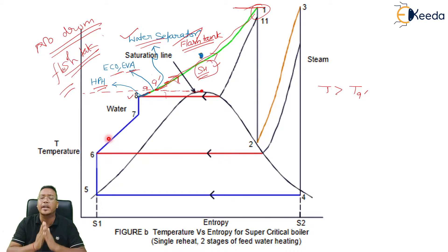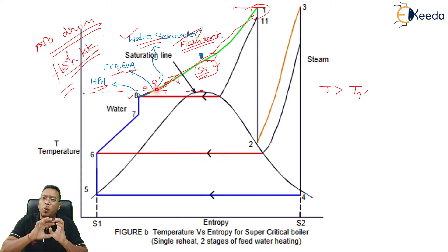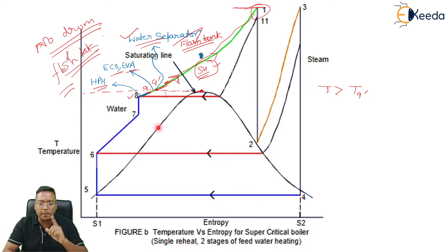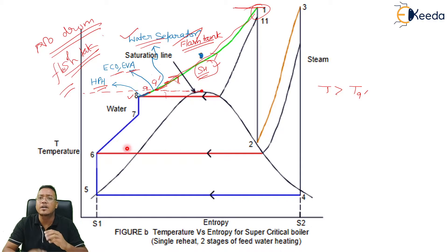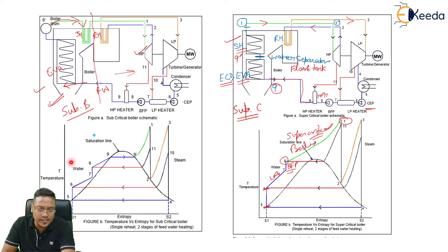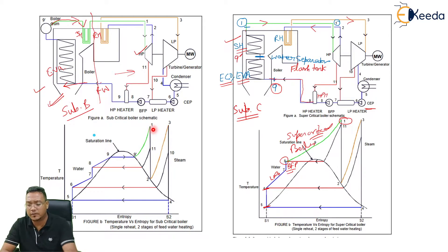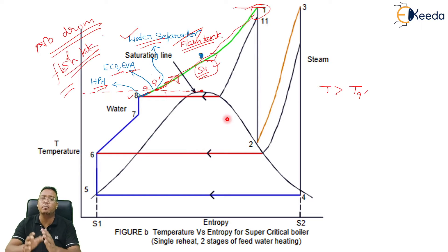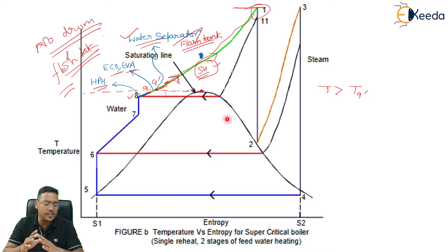As the temperature increases from point nine-dash, the water flashes into steam directly. Remember this point very carefully. If this is a subcritical boiler, the process on the T-S diagram will go through the two-phase region — you can see eight to nine, then nine to nine-dash, and nine-dash to one. In the supercritical case there is no mixture of water and steam, which is why there is no boiler drum. This is the working of a supercritical or once-through boiler.